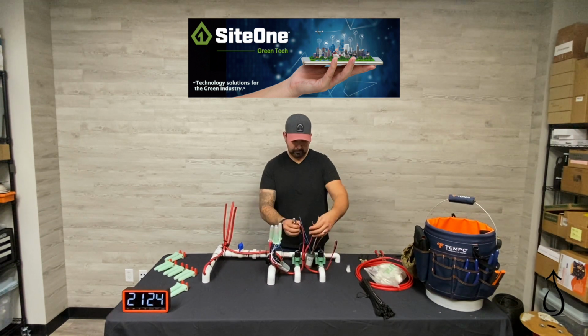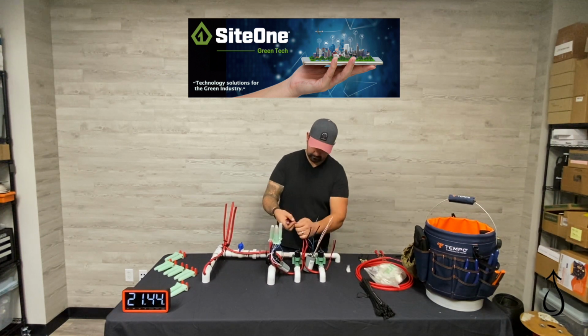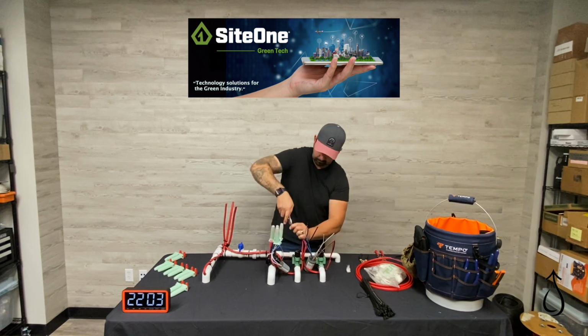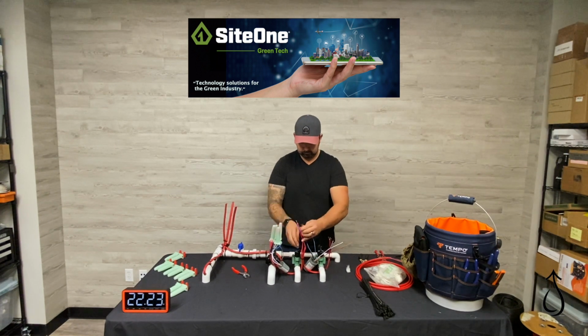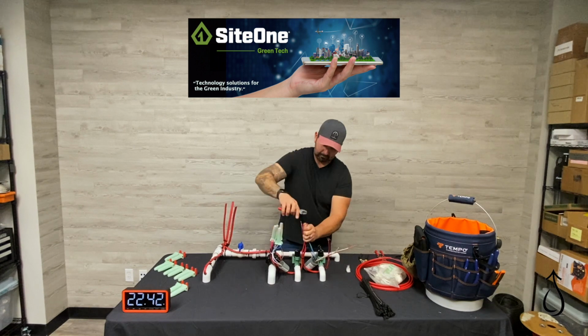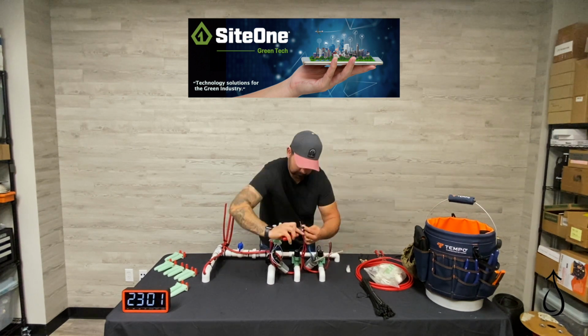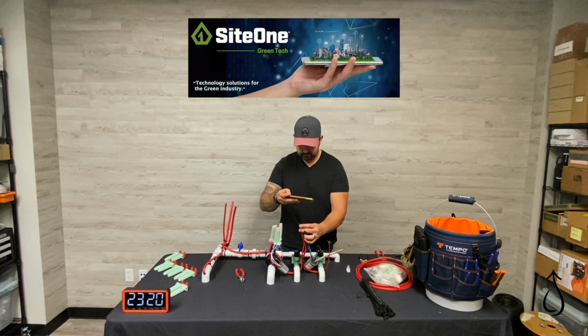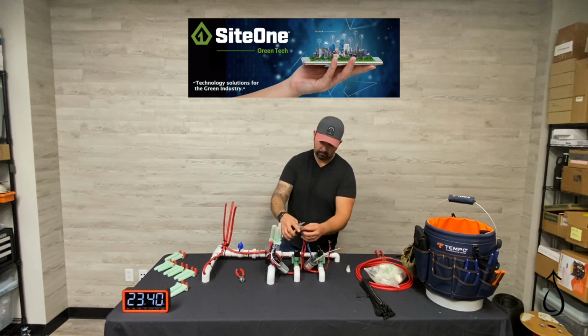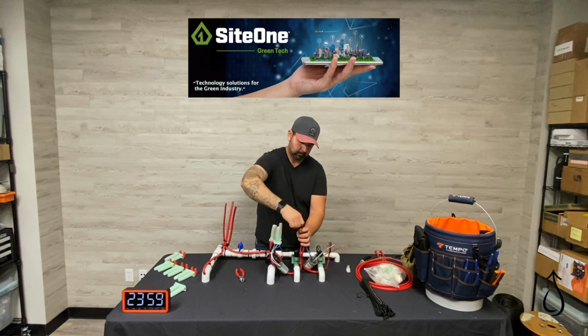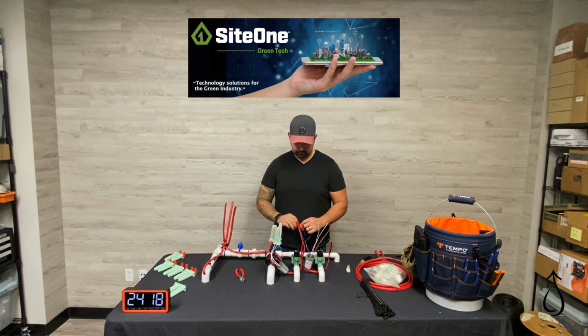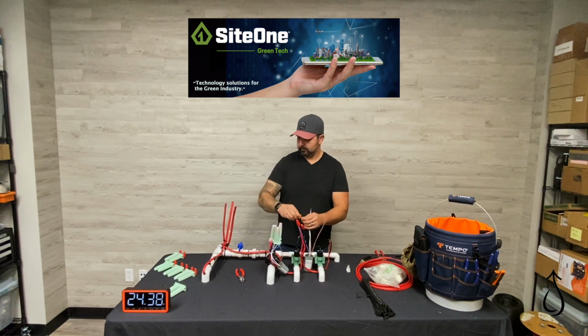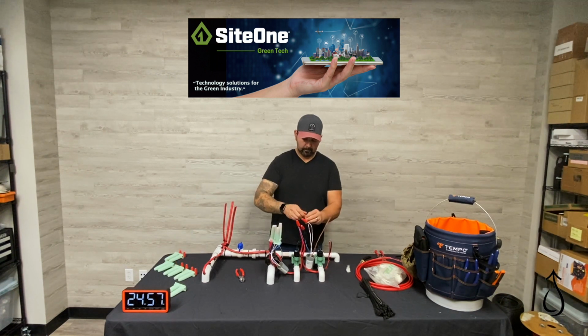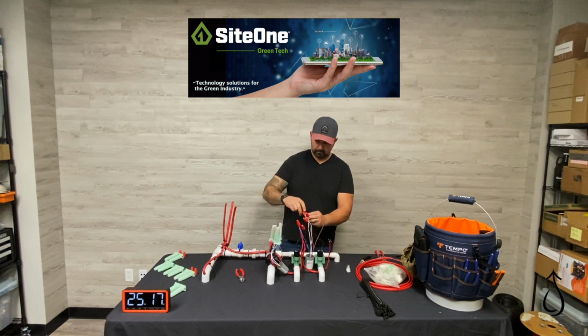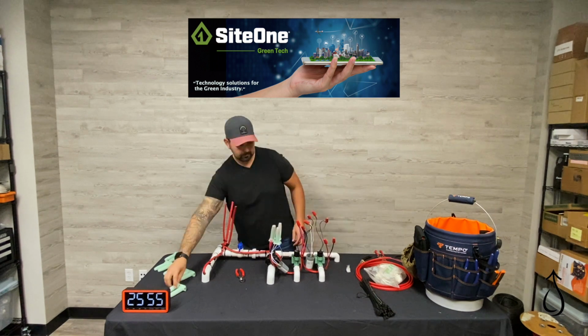The last step to splice a decoder to its irrigation valve is to zip tie the wires so that the DBRY6 caps are vertical with the dry wire nuts on top. This method basically guarantees that even if this valve box fills up with water, the wire splices will always stay dry. I strongly suggest finishing all the splices with the push tool and cotton balls, making sure that all splices stay dry and vertical. I always have a bundle of zip ties in my 2R bucket to tie the splices vertically nearest their solenoids.